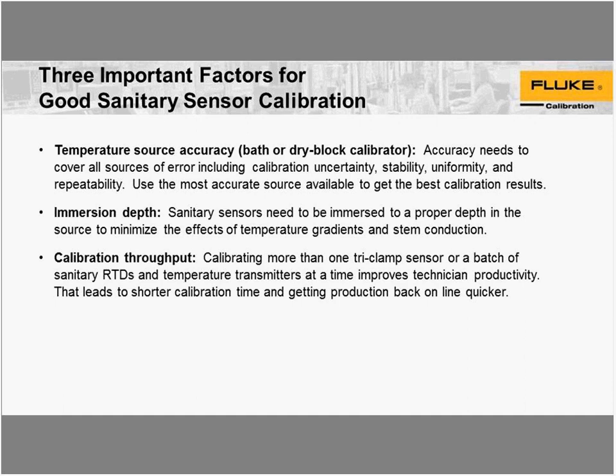Next is having sufficient immersion depth. Temperature sensors need to have proper immersion to avoid errors due to temperature gradients, because there is so much mass to it, and oftentimes the sensors are fairly short because they're fitting into a pipe system. If you're only able to immerse the sensor a few inches, you may be getting a lot of stem effect in your measurement that could cause error. Third is calibration throughput, and basically that's like any calibration. If you can do more than one at a time, that can help save a lot of time. So these are three factors that we felt are important to make a good tri-clamp sensor calibration scenario.